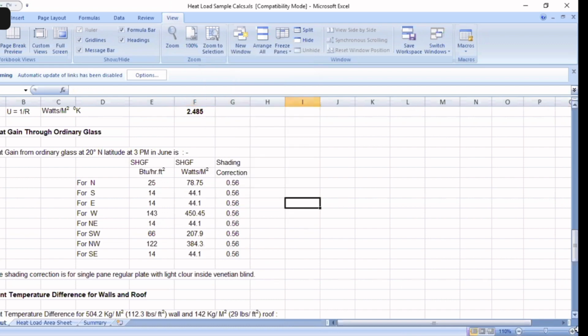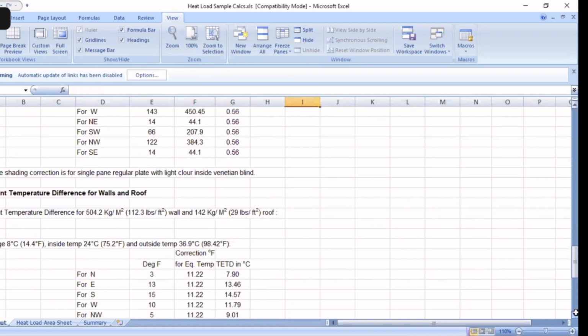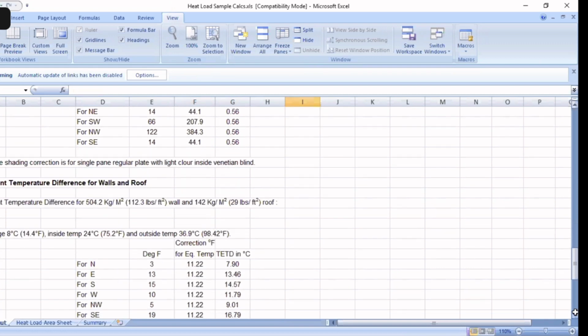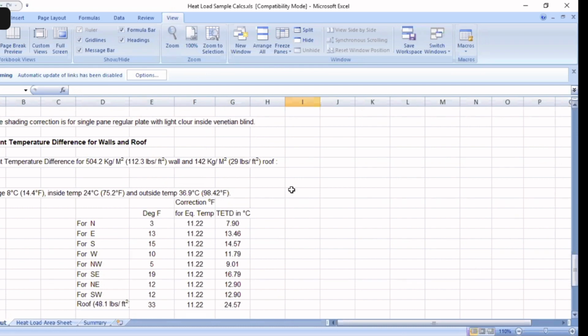Then equivalent temperature difference, TETD, total equivalent temperature difference. We have considered 504.2 kg per meter square for wall and 142 kg per meter square for roof construction. This is density, we have considered. And daily range 8 degrees centigrade, inside temperature 24 degrees centigrade, outside temperature 36.9 for Calcutta.